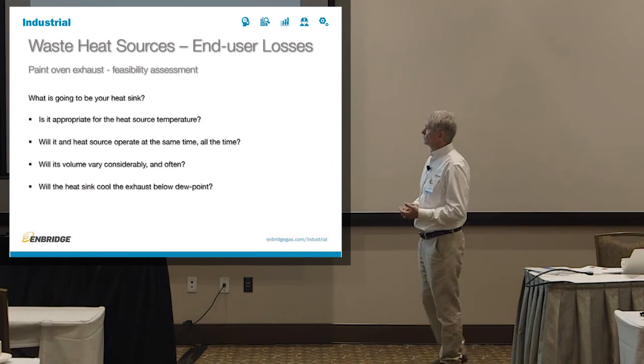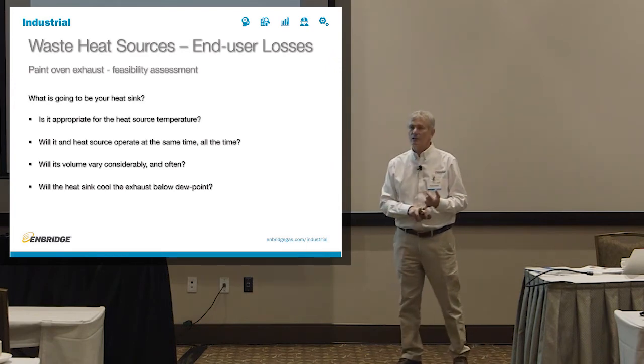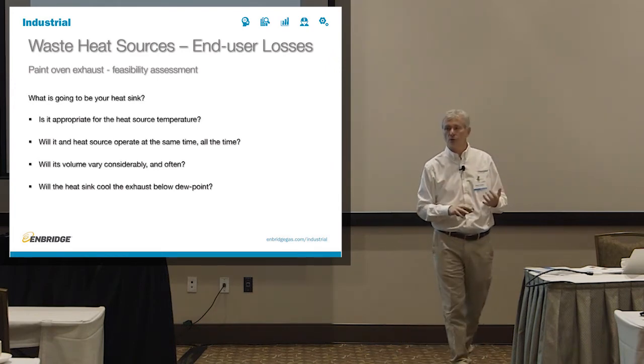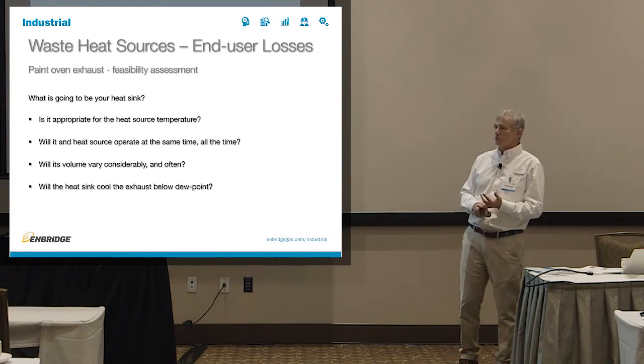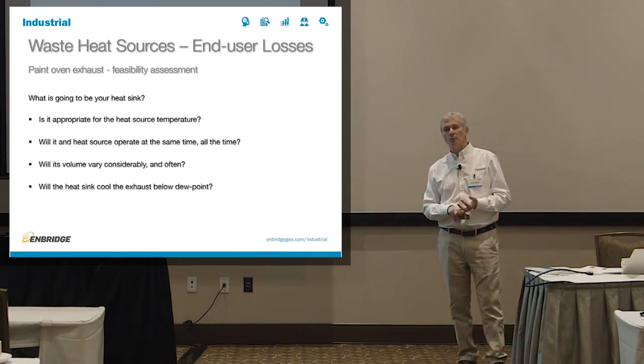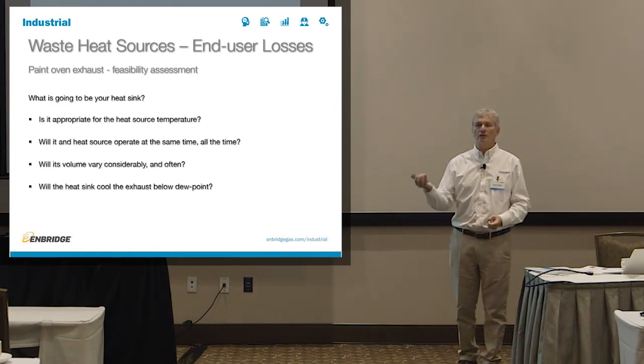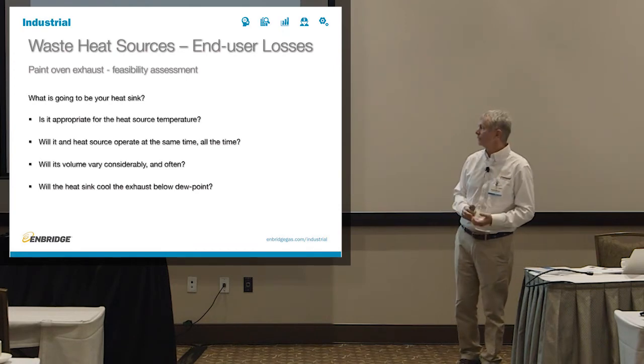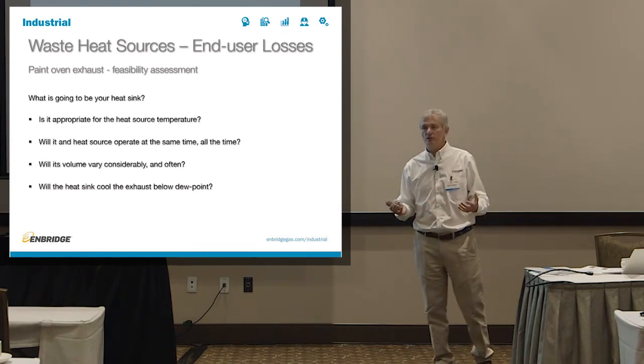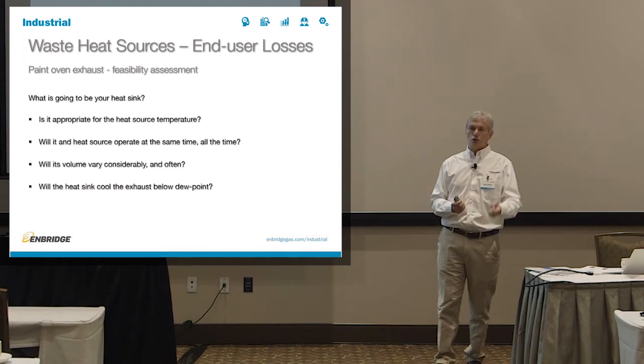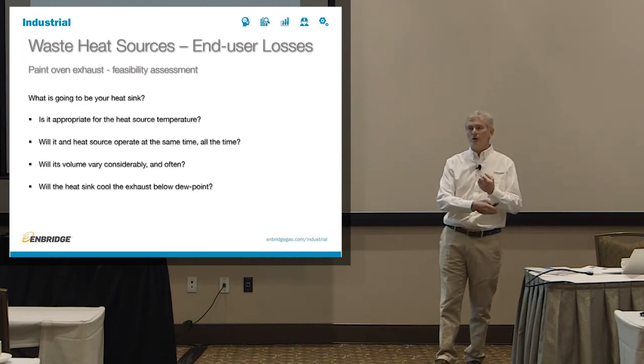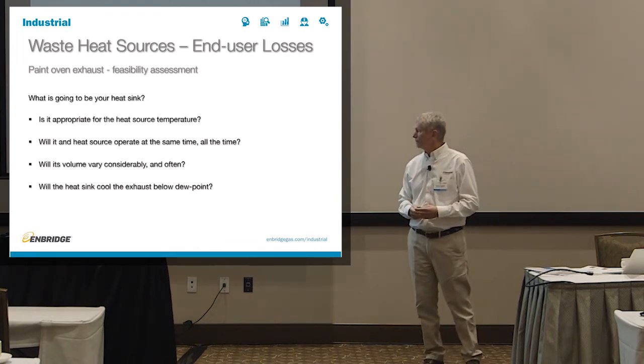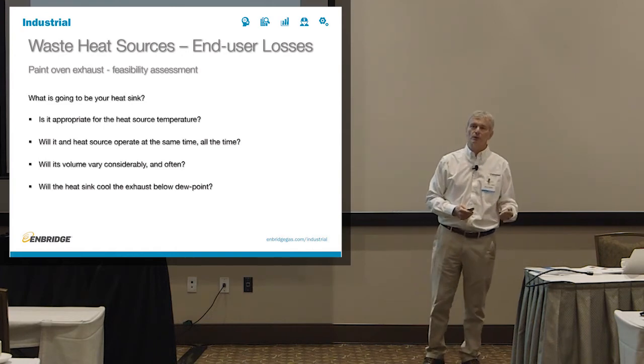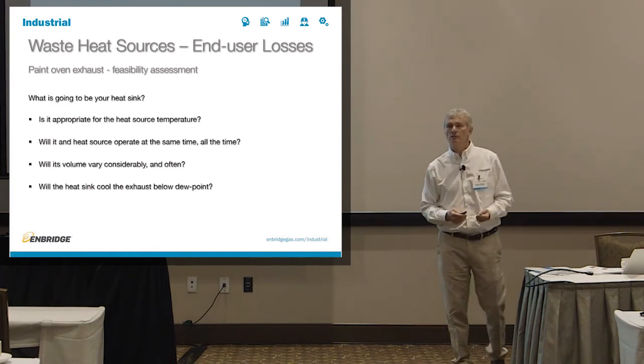So you have to figure out, is it an appropriate heat source temperature if you have a heat sink? Is 300 degrees too much, too little? Do they operate at the same time? Doesn't help you any if your heat sink operates only when the heat source is not available, and the other way around. Will the volume vary considerably? Is that exhaust going at the same volume? Is your heat sink going at the same volume? Will the heat sink cool something below the dew point? Will it condense?